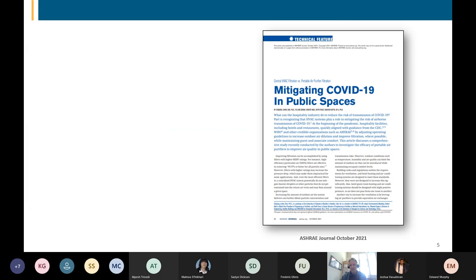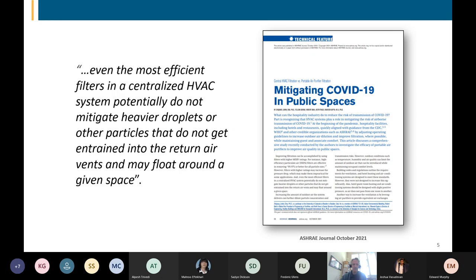Then another peer-reviewed ASHRAE Journal article appeared in October of 2021 called Mitigating COVID-19 in Public Spaces. Now, the authors of that article said that even the most efficient filters in a centralized HVAC system potentially do not mitigate heavier droplets or other particles that do not get entrained into the return air vents and may float around a given space. What they're basically saying is there may be larger particles that filtration couldn't be effective at mitigating anyway. If you're within close range, they may hit you, they may fall onto a surface, you may touch them. But if the ones in the air don't get entrained into the return air vents, they can float around in the space, may not get back to filters, and therefore filters may not be that effective.